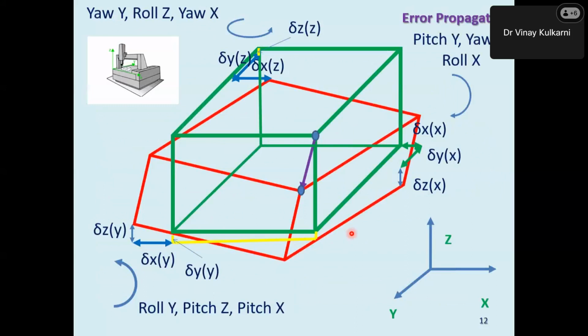Probably this is the most important diagram that we can develop here. All the green lines show the measurement volume without any machine error. But there are errors in the system. That is, one is, let's say, yaw, roll, pitch. Yaw, roll, pitch, for all three dimensions, that is X, Y, Z, make the machine very complicated here. And because of that, what happens is there is a drift in the measurement system.